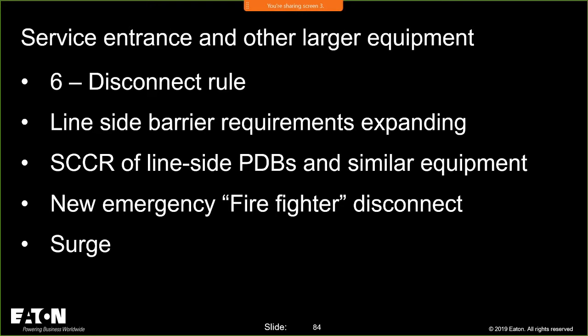Here's what we changed: we changed the 6 disconnect rule. We didn't get rid of the 6 disconnect rule, we just modified it. The NEC still permits up to 6 disconnects for service entrance equipment. But in the 2020 cycle, we added requirements around compartmentalization and barriering for the main overcurrent protective device or devices in that equipment.